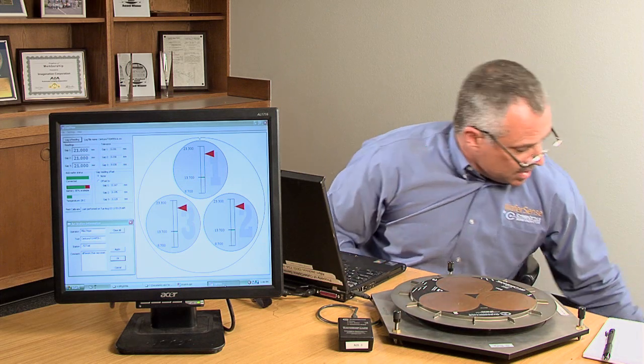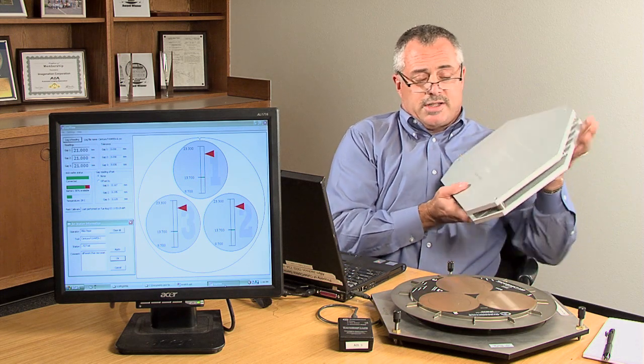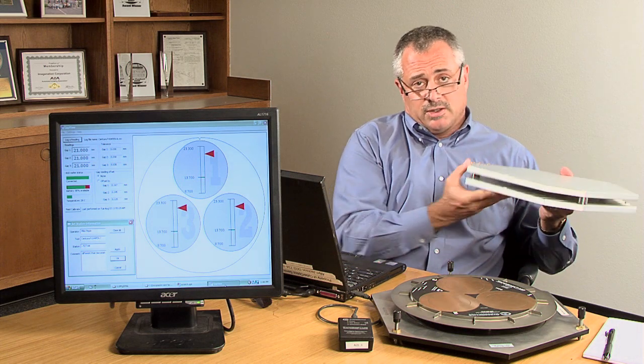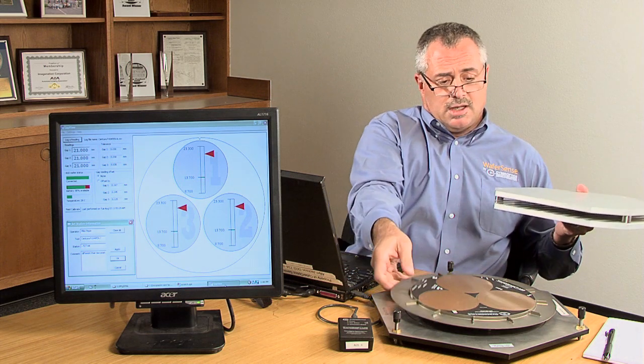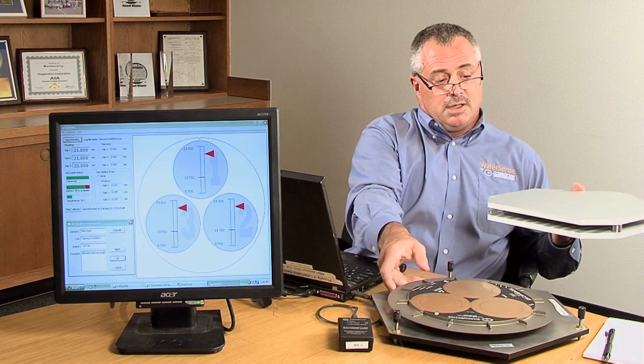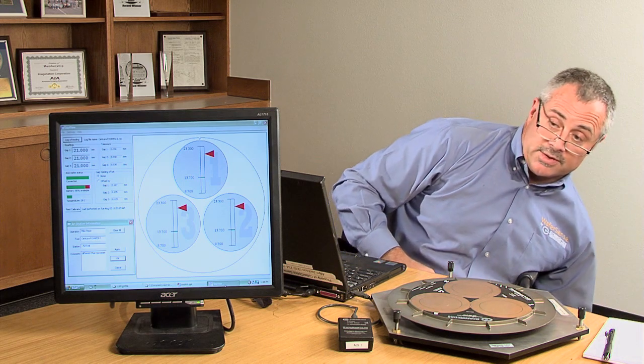Also, an important accessory with AGS is the AGS-15 NIST traceable field calibration unit. AGS is placed inside the unit and field calibrated to a precision known gap to assure the one-one-thousandths of an inch accuracy.